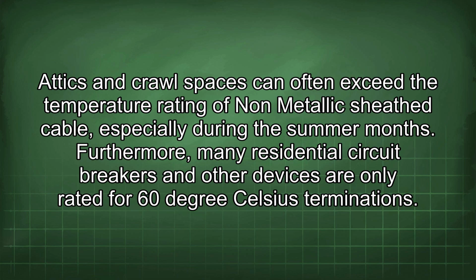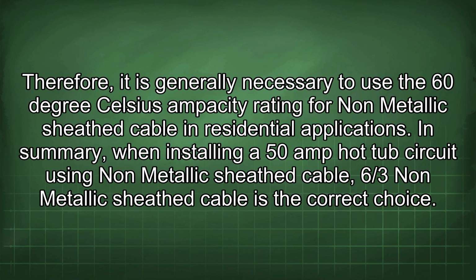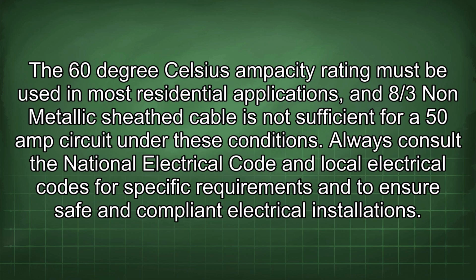Attics and crawl spaces can often exceed the temperature rating of non-metallic sheath cable, especially during the summer months. Furthermore, many residential circuit breakers and other devices are only rated for 60°C terminations. Therefore, it is generally necessary to use the 60°C ampacity rating for non-metallic sheath cable in residential applications. In summary, when installing a 50-amp hot tub circuit using non-metallic sheath cable, 6/3 non-metallic sheath cable is the correct choice. The 60°C ampacity rating must be used in most residential applications, and 8/3 non-metallic sheath cable is not sufficient for a 50-amp circuit under these conditions.